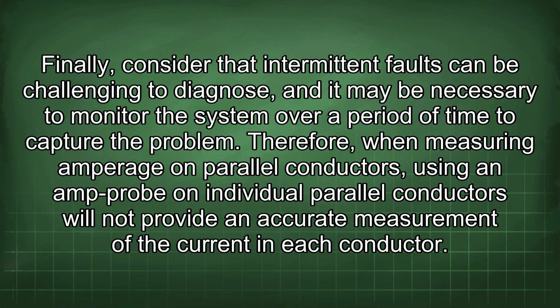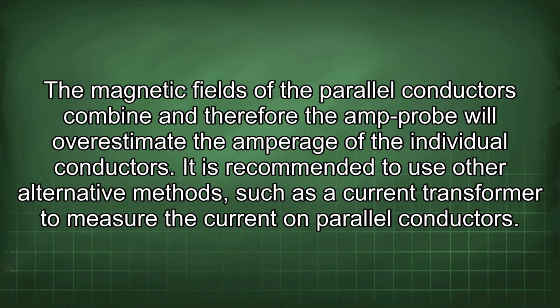Therefore, when measuring amperage on parallel conductors, using an amp probe on individual parallel conductors will not provide an accurate measurement of the current in each conductor. The magnetic fields of the parallel conductors combine, and therefore the amp probe will overestimate the amperage of the individual conductors. It is recommended to use other alternative methods, such as a current transformer, to measure the current on parallel conductors.